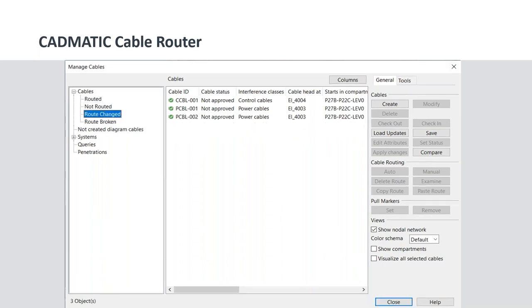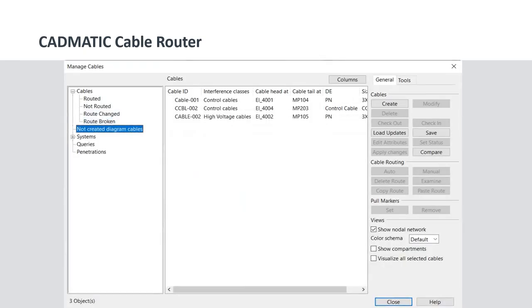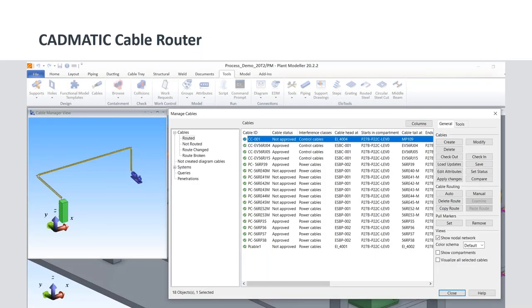Cables that have been routed but whose path has subsequently changed are listed under 'Route Changed.' Cables whose path has been deleted or removed after routing are listed under 'Route Broken.' Cables created in the CADMATIC single line diagram that have not yet been updated to 3D are shown under 'Not Created Diagram Cables.' Whenever you click on any routed cable in the cable manager, a preview opens on the left showing the two equipment endpoints between which the cable is routed and the path it takes — making it very easy to track cables.